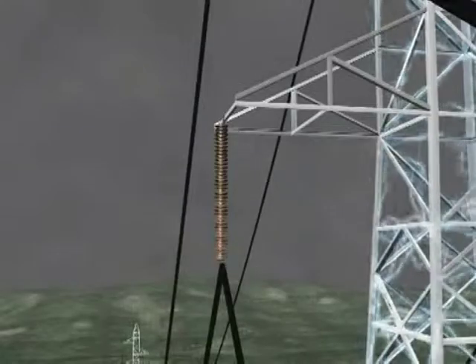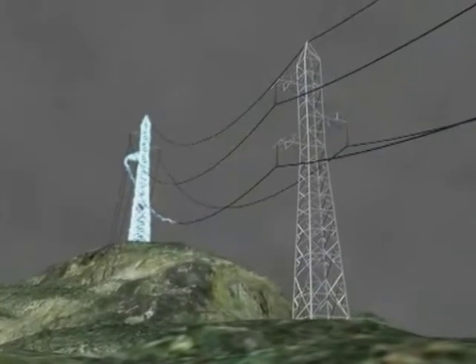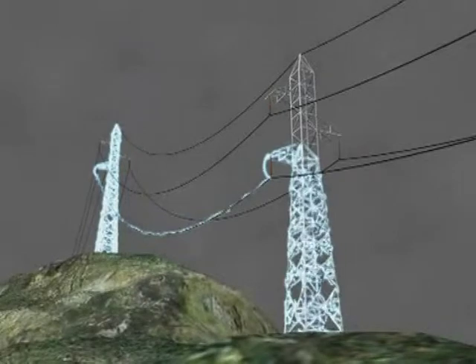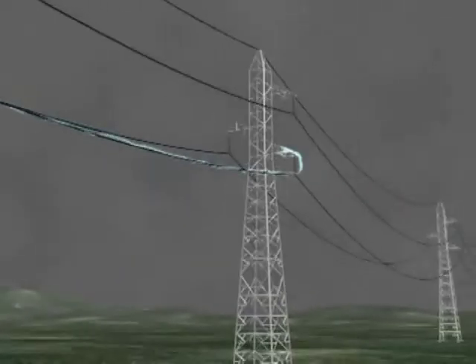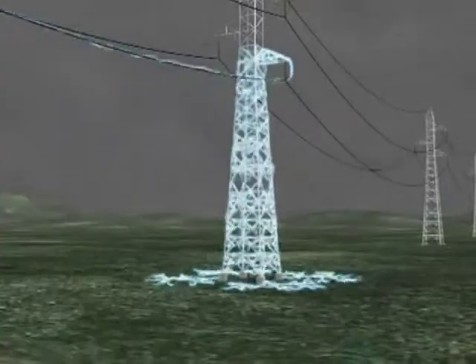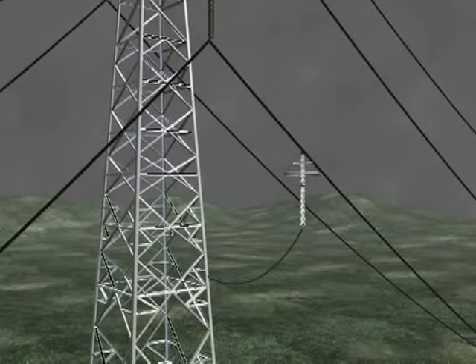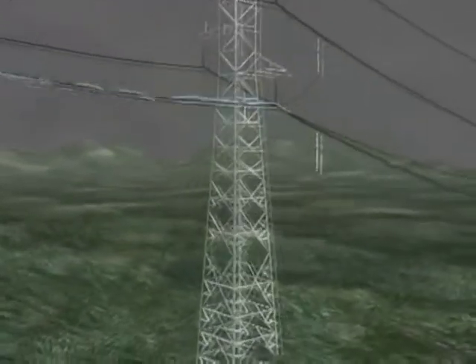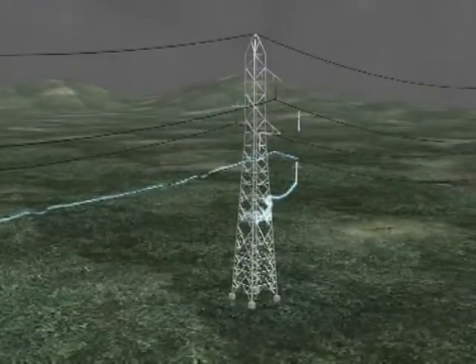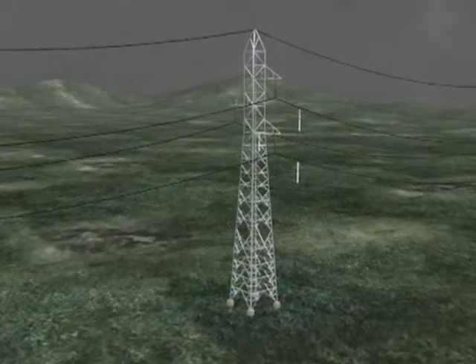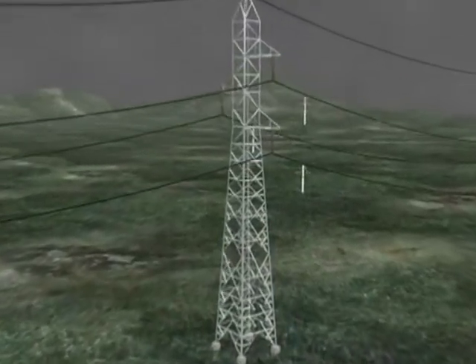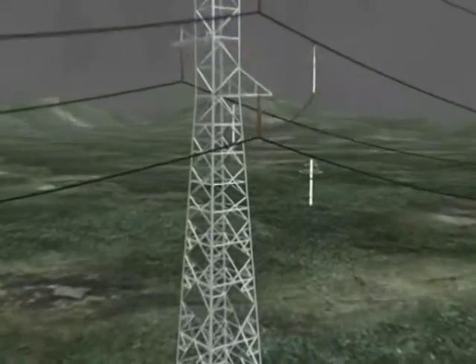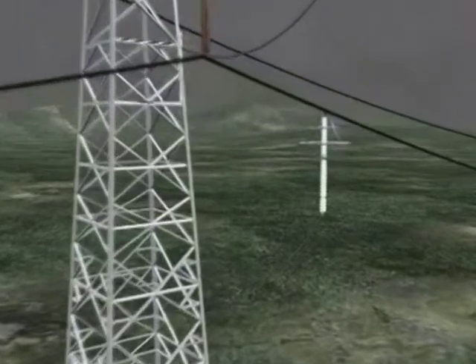When lightning strikes the lightning protector line or directly the tower with a small resistance to ground, lightning current flows through the tower body down into the ground. If the grounding resistance is large, a potential sufficient to override the line insulation may occur in the traverse. Insulation breakdown due to lightning surges is likely to be converted into a power arc, causing disconnection of the overhead line. Surge arrestors are installed in parallel to the line insulation. Lightning current through surge arrestors spreads into the line phases and flows through the tower body. In this case, isolation closure and disconnection of the overhead line doesn't occur.